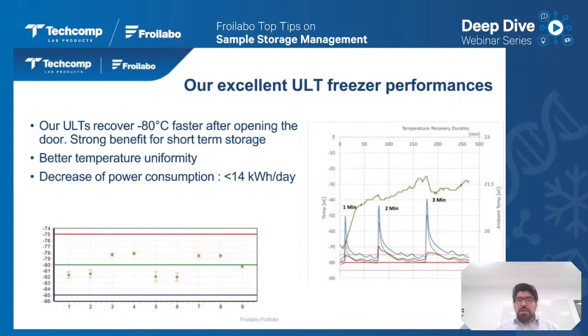Then we tested this to see, if you leave the door of the freezer open for 1 or 2 minutes, how quickly the freezer will go back to the required temperature range. By the standard, if you set it at -80, the range is ±5 degrees. Then you can see on the right-hand side the temperature recovery. It shows how much time it takes to get there, and we are at less than 30 minutes to recover and go back to the temperature we have to reach.